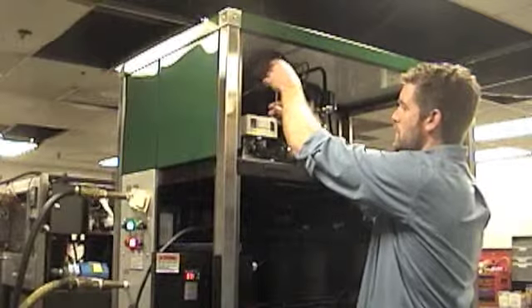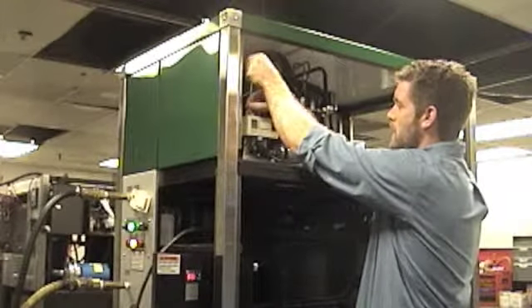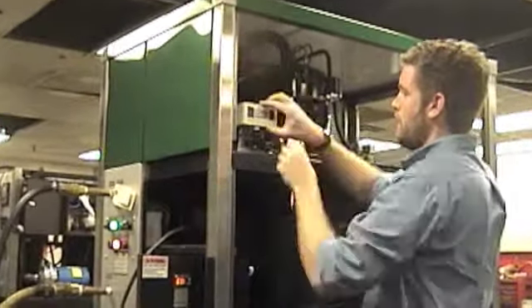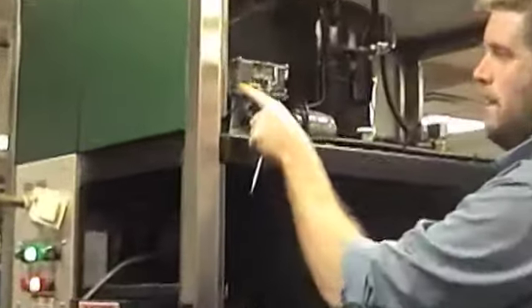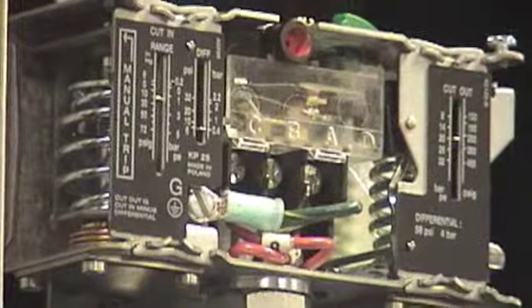To do that, you remove the face cover plate, and the manual trip is right on the left side. So you'll activate that. You may have to hold it for up to 10 seconds or so until it'll stay on its own and the pressure is equalized. And it should hold itself up.